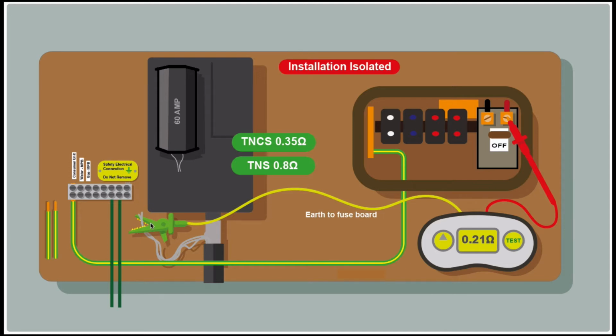And so very importantly now, we need to re-terminate the earthing conductor back into the main earthing terminal. Nip that up nice and tight. Make sure all our connections are good. All the earths are back in place. And then we can re-energise the installation.